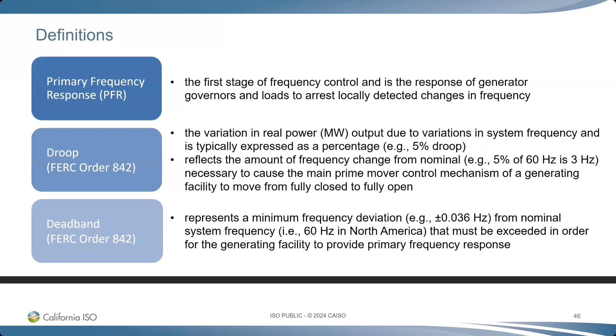But a couple of things to think about with frequency: there's the primary frequency response. The first stage of frequency control is the response of the generator governors and loads to arrest locally detected changes in frequency. So looking at the definitions and dead bands, here's an overview of the primary frequency response. It is, again, the first order of response, and it's making sure that we're maintaining that 60 hertz, that we're not risking reliability.